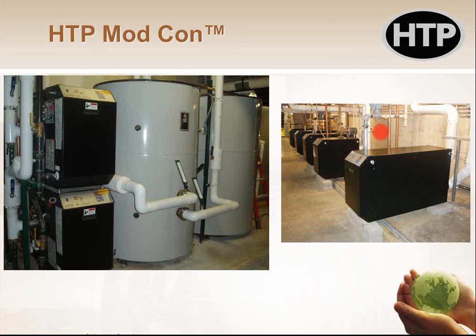And then the one on the right over here is actually a swimming pool job. I believe this one is the Kalahari Water Park in Wisconsin. We didn't do that job, but our neighbors to the north did. They sent us the picture because it's a pretty cool job. But you can run chlorinated water directly through these ModCon boilers as well without a heat exchanger. That does help your efficiency by not having a heat exchanger, but it reduces your warranty, so you're down to a 3-year warranty on the boiler heat exchanger if you run chlorine through it instead of the typical 10-year. But once again, it's still better than a typical copper pool boiler that you might use, which probably has a 1-year warranty.